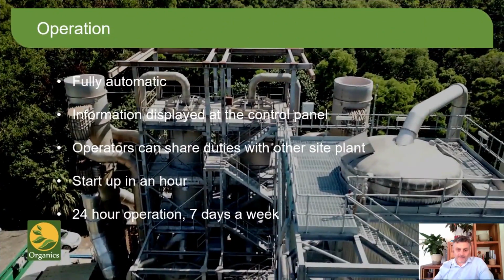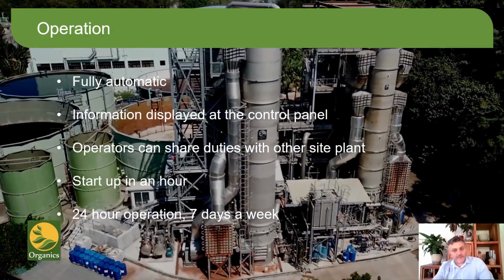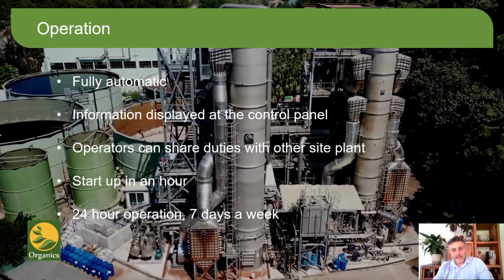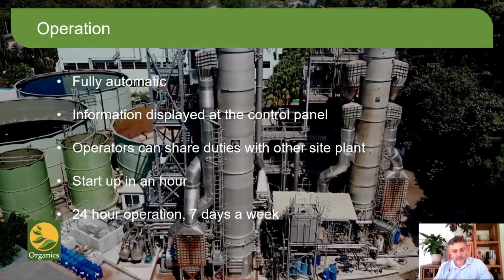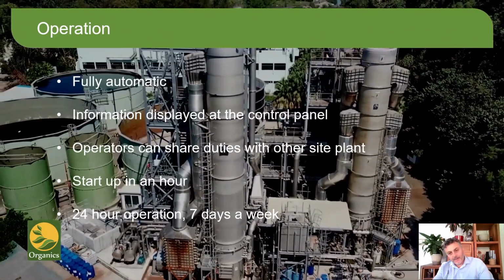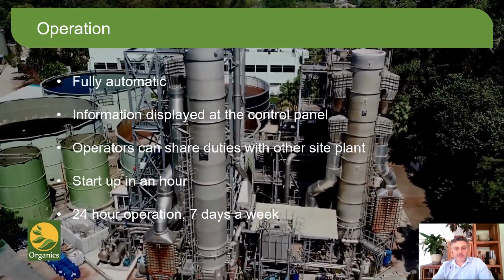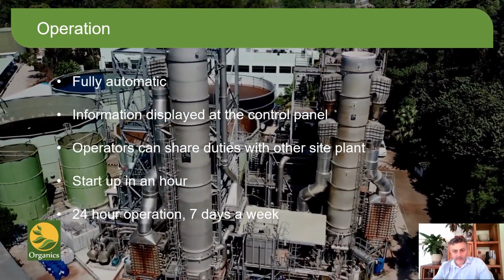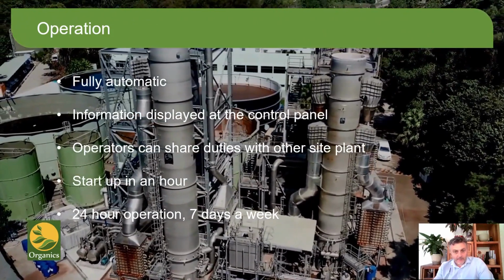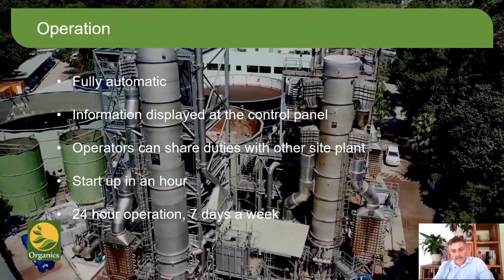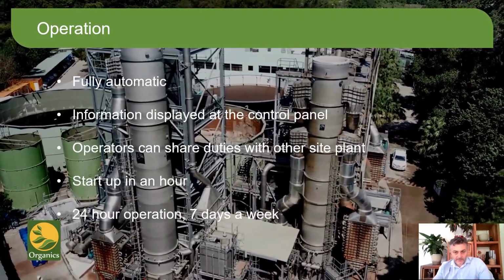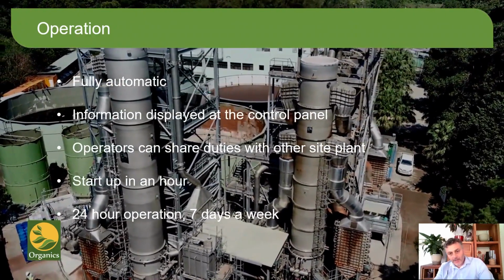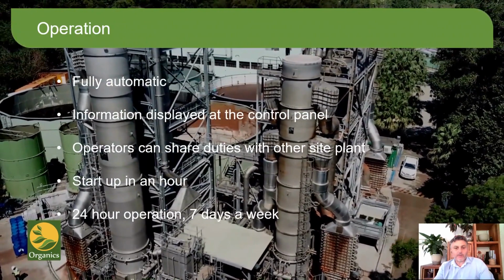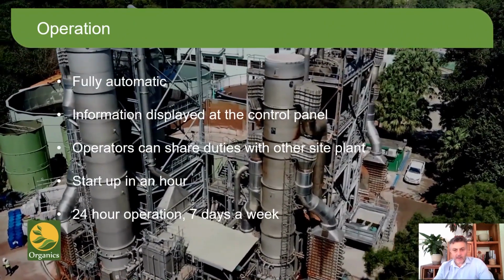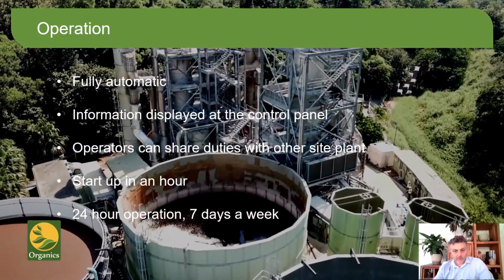Having said all that, for the operator, running the system is simple. The system itself is fully automatic. Push the green button and it runs through its startup procedure and tells you when it's ready to discharge. It then monitors critical temperatures and adjusts itself accordingly, and will safely shut down if a parameter moves out of specification and is unable to control it itself. We have learned that as long as certain key parameters are maintained, then the stripping will work repeatably with only spot checks on the outlet ammonia concentration typically required.